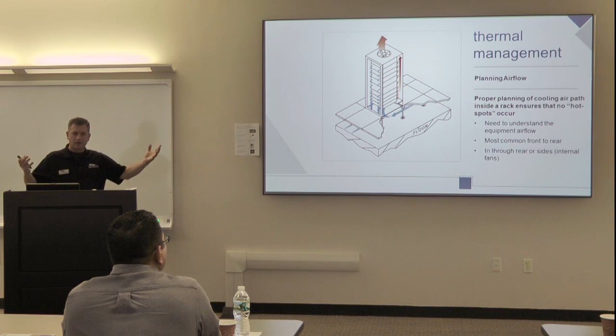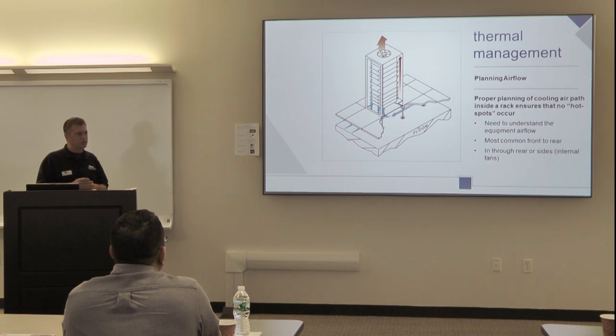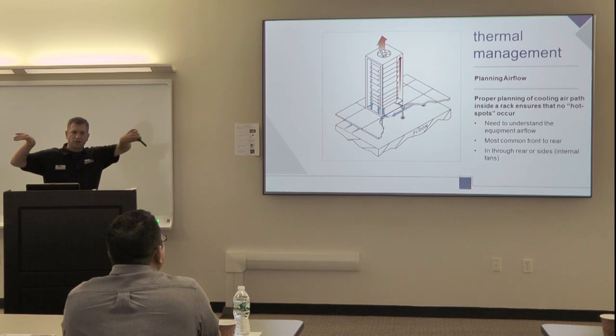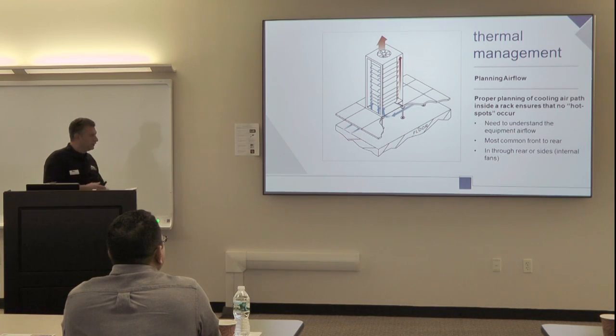If you got a bay of racks, one of the things you want to be concerned about, you don't want that hot air blowing into the next rack. So you want to kind of block that. Some of the bigger switches do that, and there were a couple amplifiers that did that as well. They've got fans on the side, so it blows out one side. So you may have equipment in another rack, and you want to make sure you're not overcooking that equipment there. So by doing something in the middle to block the racks.